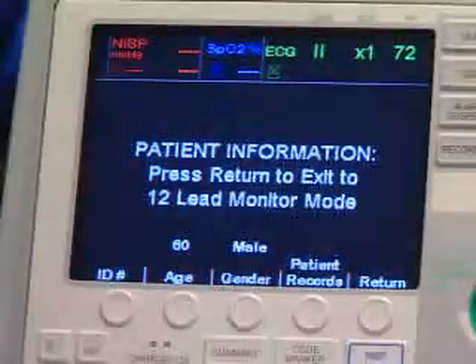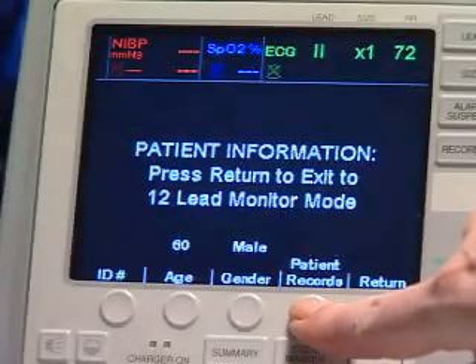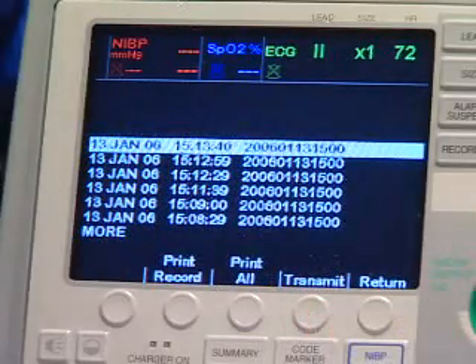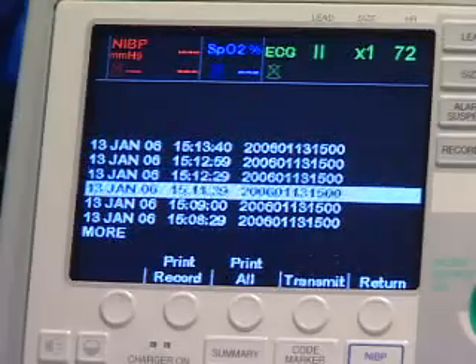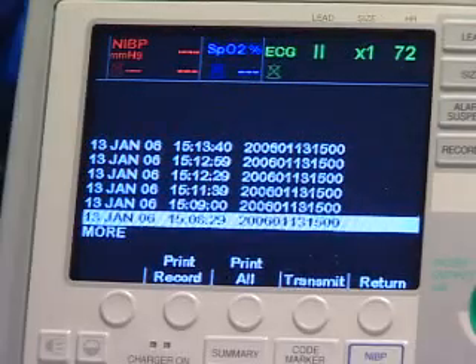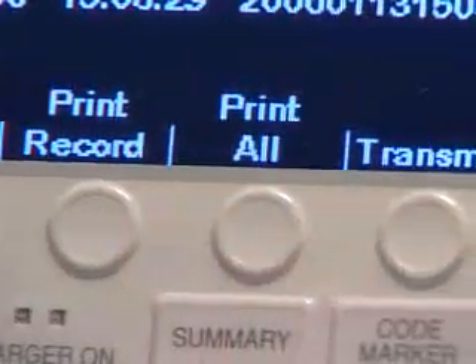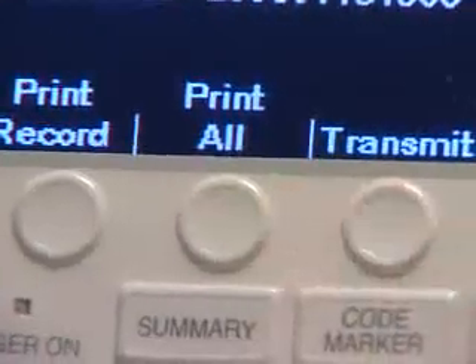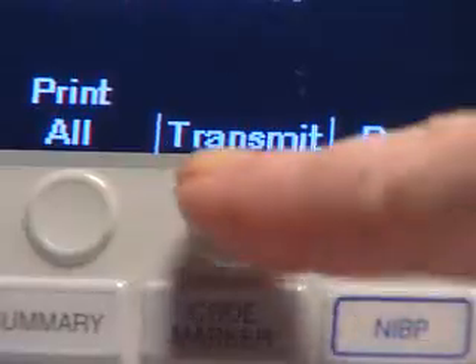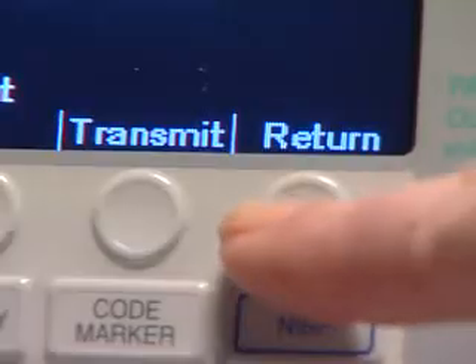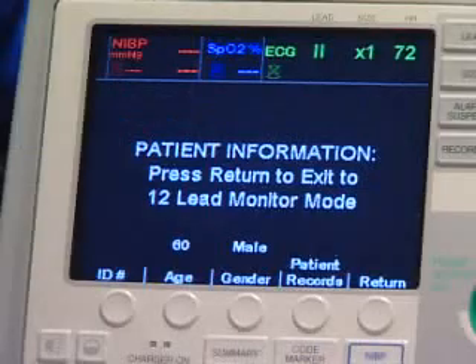The patient record soft key allows you to transmit or print specific 12-lead ECG records as denoted by the date, time, and patient ID number. Up to 40 patient 12-lead ECG records can be stored on the internal memory of the E-Series. Print record prints the selected 12-lead records on the strip chart. Print all prints all stored 12-lead records on the strip chart. Transmit transmits the selected 12-lead record. Return: the unit exits the patient record screen and returns you to the patient information screen.